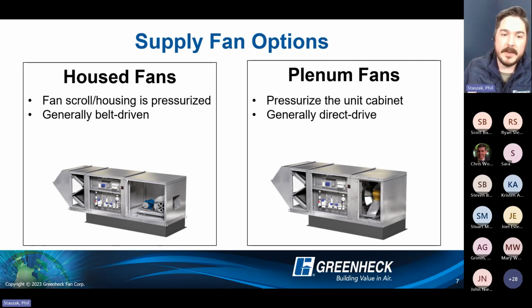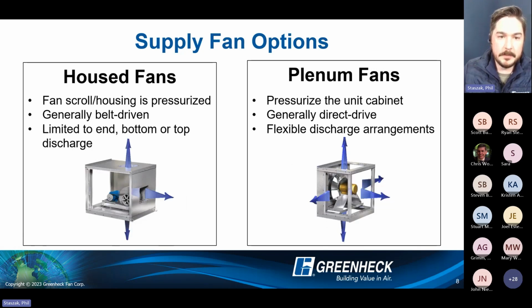And with direct drive fans, a lot less maintenance required because there's no more belts and sheaves to adjust. You've got a wheel mounted directly on a motor shaft, and then variable frequency drives are typically standard with those, where it would be an option to select with a forward curve belt driven fan option.